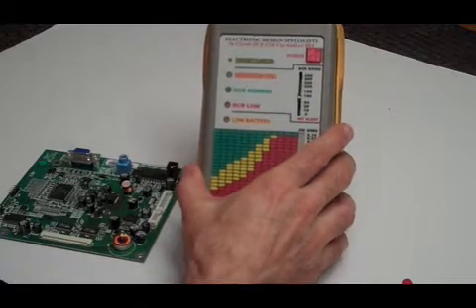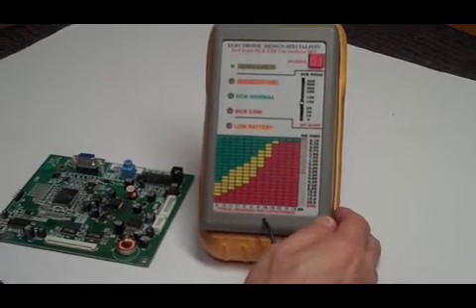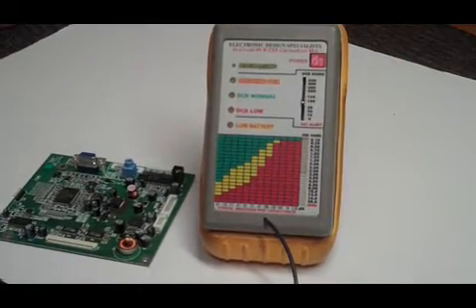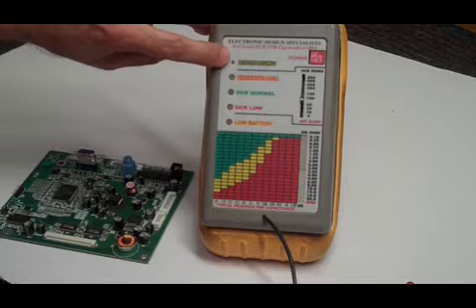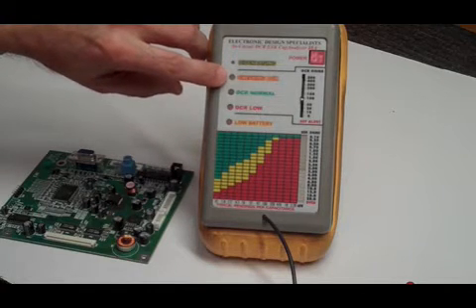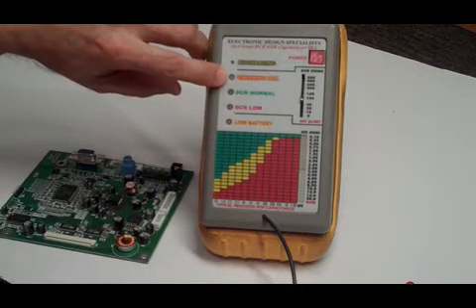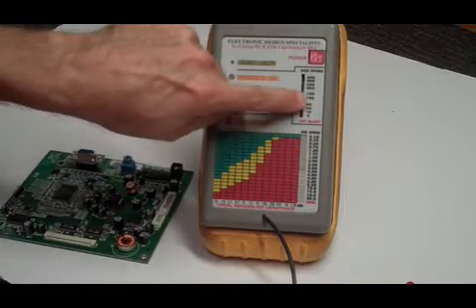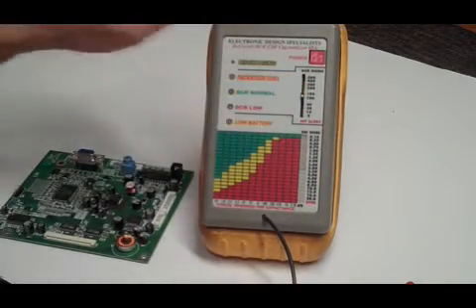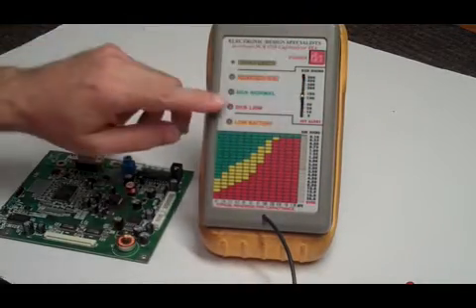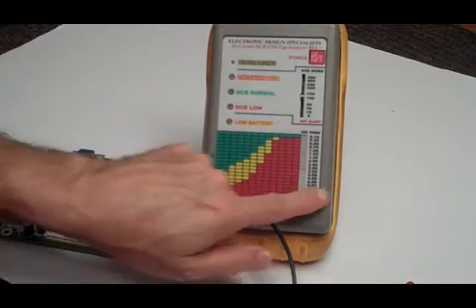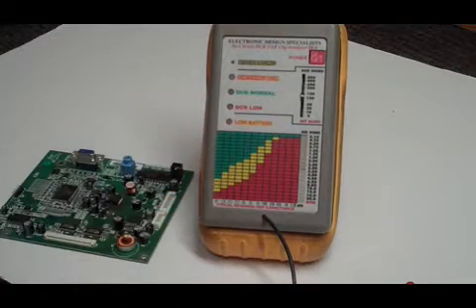Well, here's the CAP analyzer, which has two different test modes. The main test mode, simply by turning it on, is where it tests a capacitor completely. It'll discharge it first, check the DC resistance of the capacitor, DCR, from 0 up to 500 ohms. You can preset it wherever you want to be warned at, and then if it passes that test, it checks the ESR and gives you the reading here.